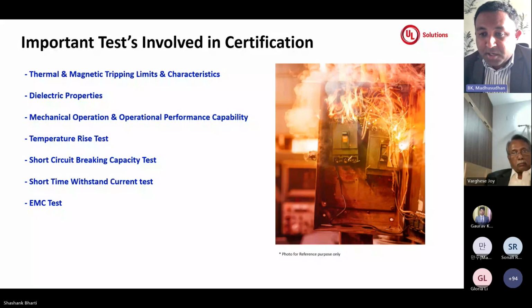Similarly for magnetic tripping, based on the customer declaration of the magnetic setting, the current will be fed to the breakers, and the breaker opening time will be measured. And there is a standard requirement that the breaker has to trip within a particular trip time. So those will be measured during these tests. And next is the dielectric properties.